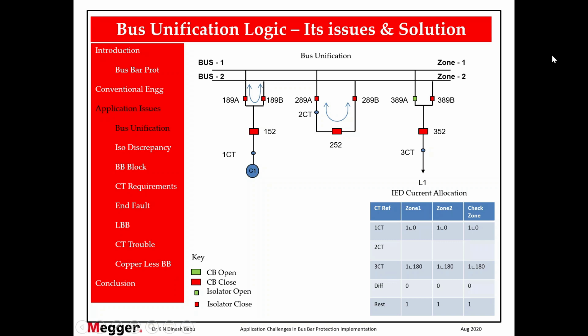So this is called the bus unification concept. In the bus unification concept, whenever both isolators of any one of the bays are closed, the bus coupler CT would be eliminated from all zones, number 1. And point number 2, all the CTs will read in all the zones except the bus coupler and bus section CT. So when we implement this logic, the solution is perfect. You can see here, now also the differential current is 0.